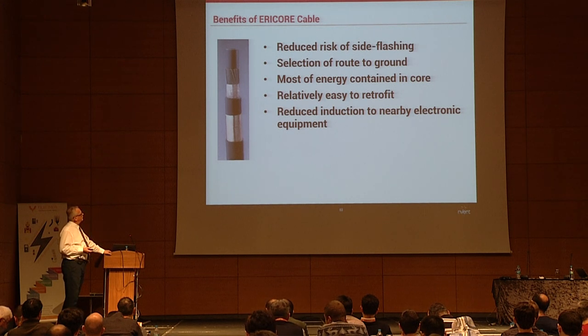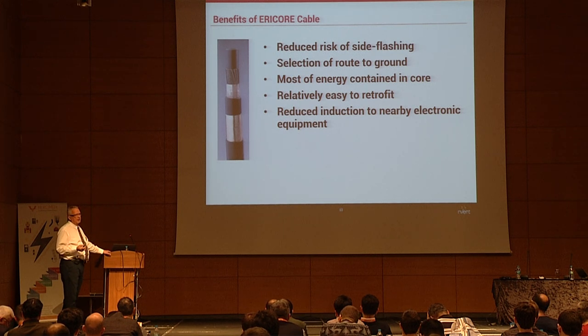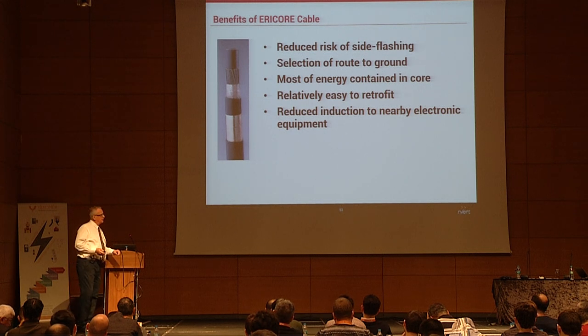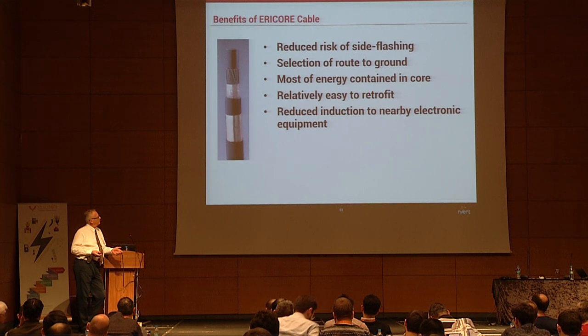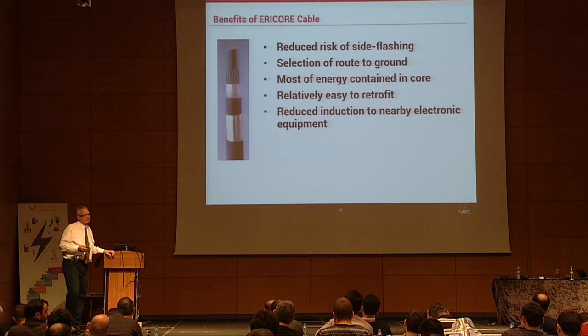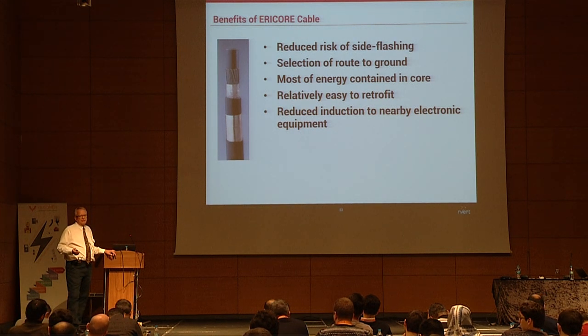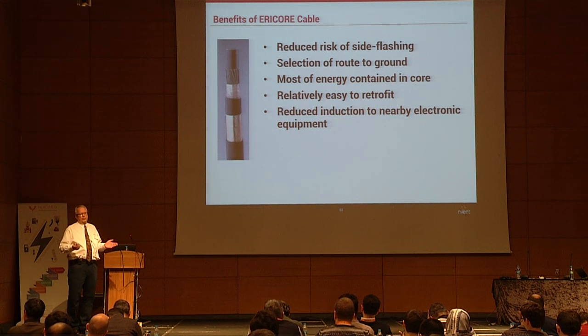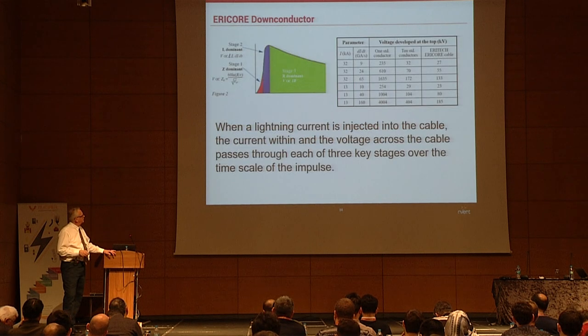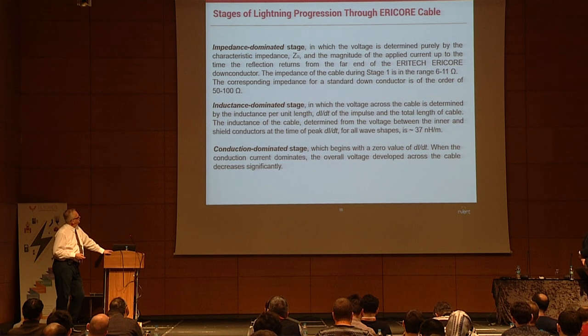The ERICORE cable reduces risk of a side flash, controls the route to ground, and keeps most of the energy contained within the cable. It's relatively easy to retrofit and can be used with a conventional lightning rod or with an interceptor. The new French standard allows insulated down conductors. This conductor works very well when you need to route the cable through a mechanical or electrical riser inside a building — it's concealed and minimizes the electromagnetic field around the cable.